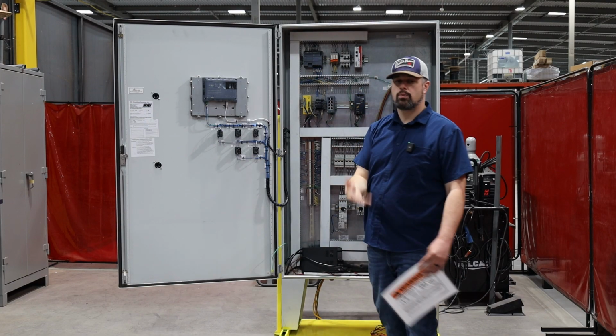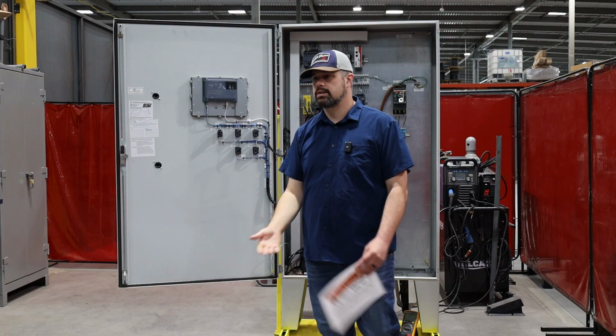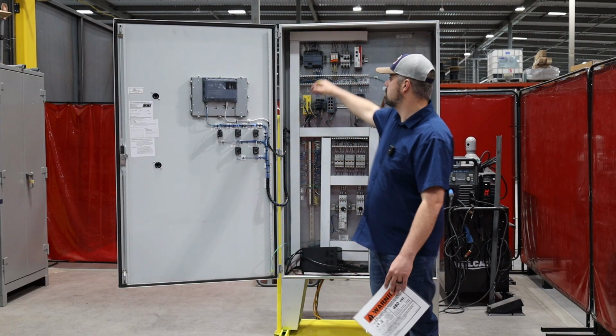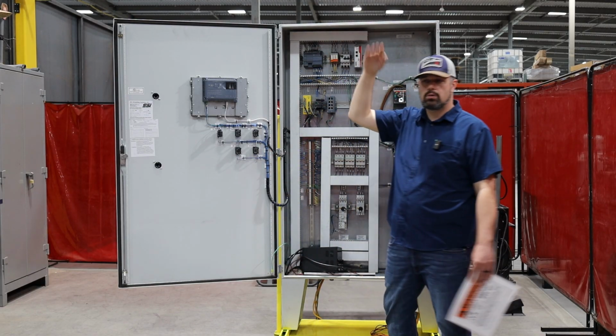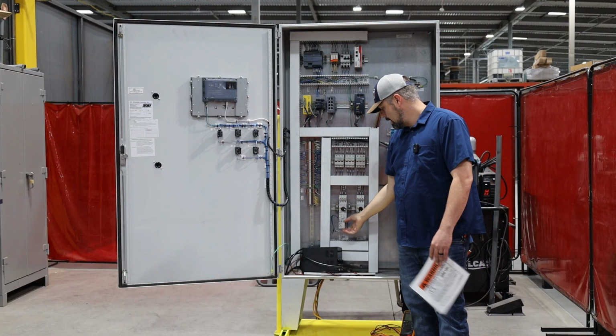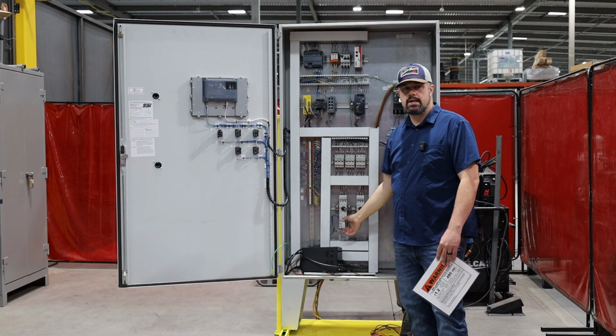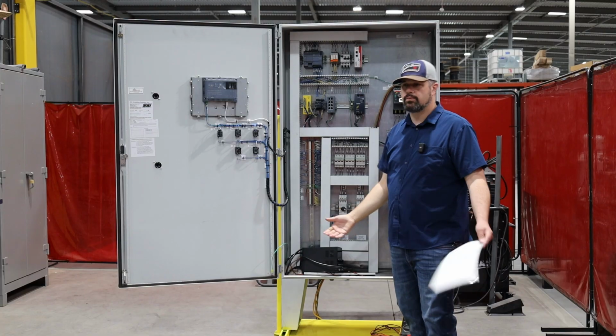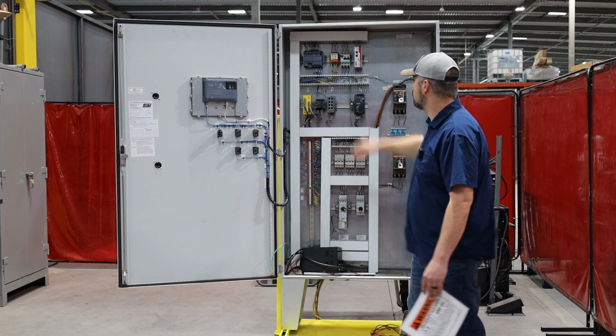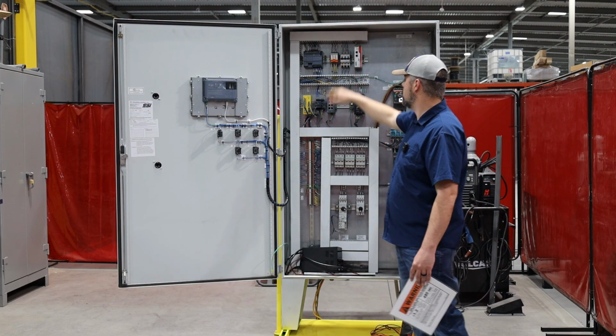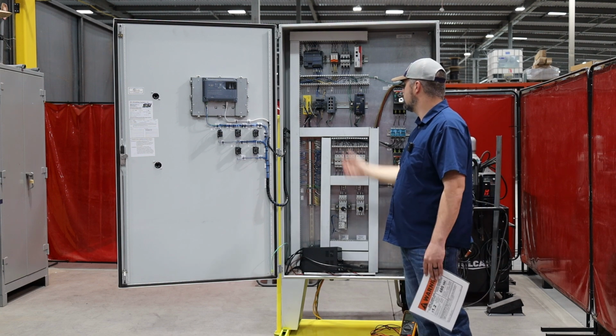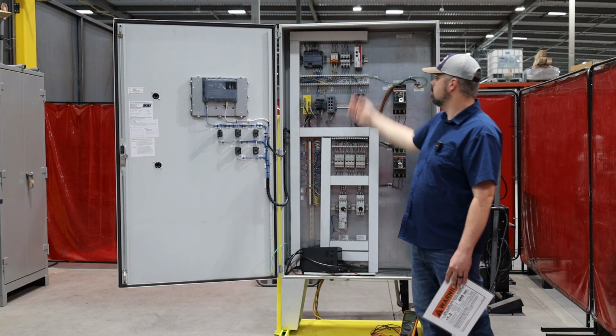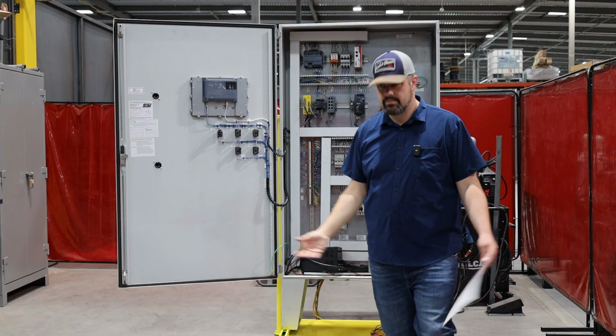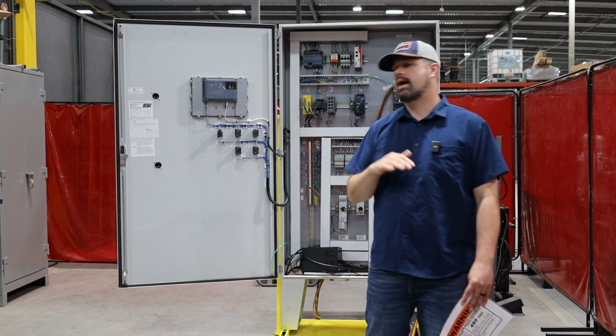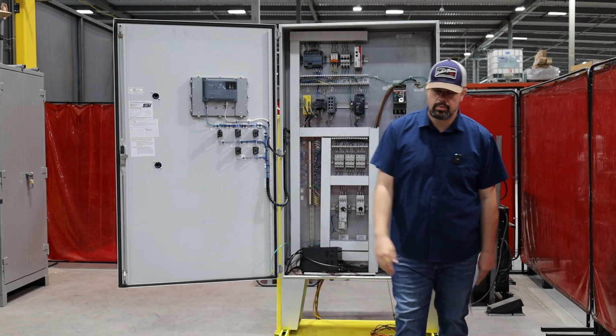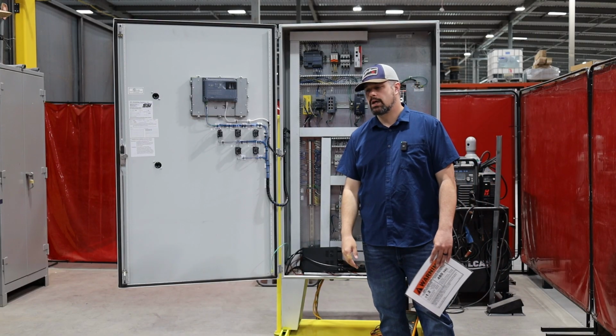And then the PLC is programmed with the logic to decide what to do with those inputs to energize certain outputs, and then those outputs go off and control 24 volt DC relays for motor start circuits, and you'll start learning about these relays and these circuit breakers and some of the network gear that's used, right, for having the PLCs on the network. And I mean, we dive into all that, SCADA, the whole purpose of it and what it all is.